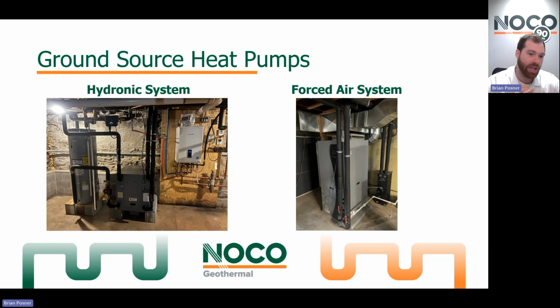Now, there are some nuances here. For example, you're going to be putting water through those radiators at 140 degrees instead of 180 degrees, which 140 is still more than capable of heating the house. However, depending on the amount of heat delivery you have and the amount of heat loss from your lack of insulation, that could adversely affect your heating delivery. So with hydronic systems, we always like to be sure that we're taking care to note what type of insulation you have in the home, how tight it is, both from an insulation standpoint and an air sealing standpoint. So we know what your heat loss is actually going to look like.